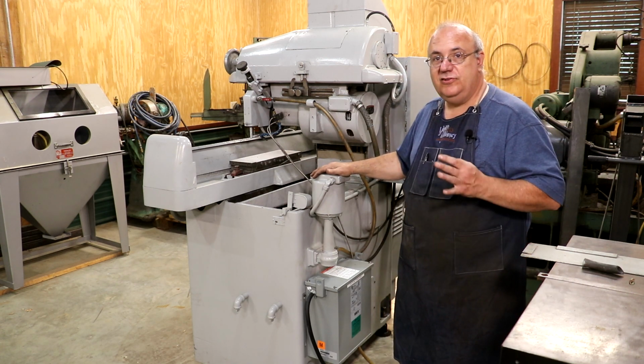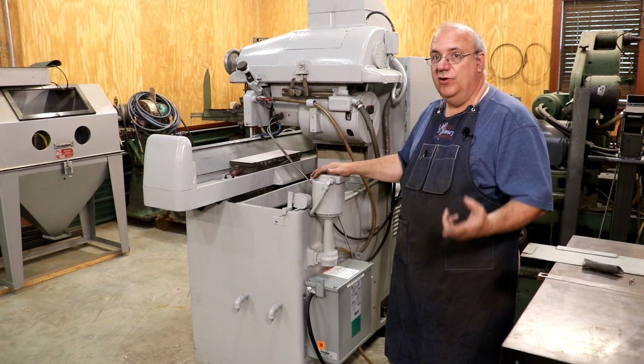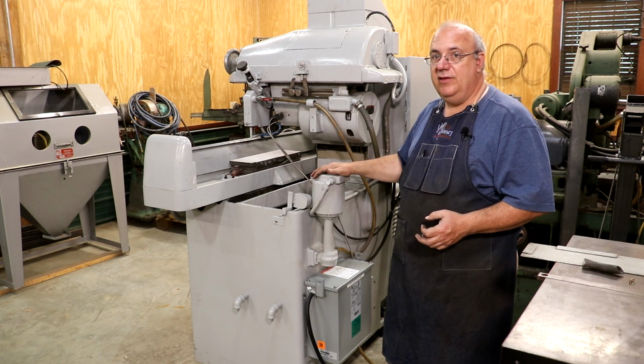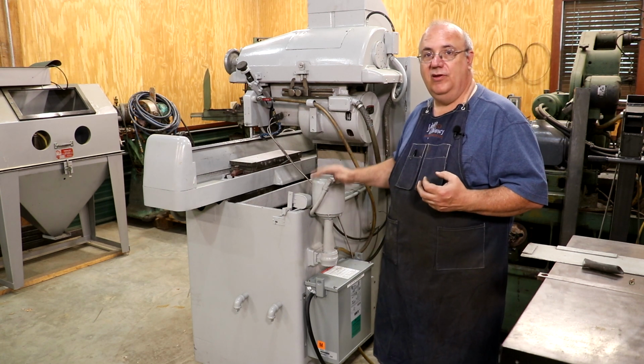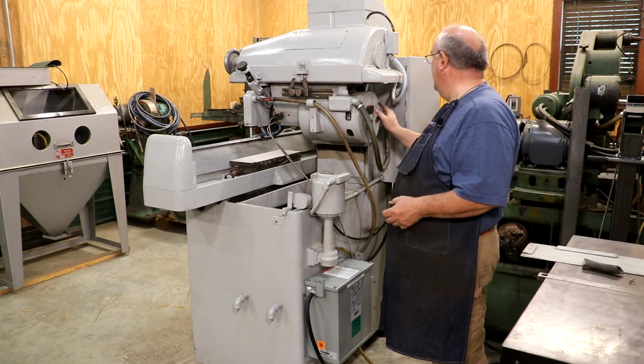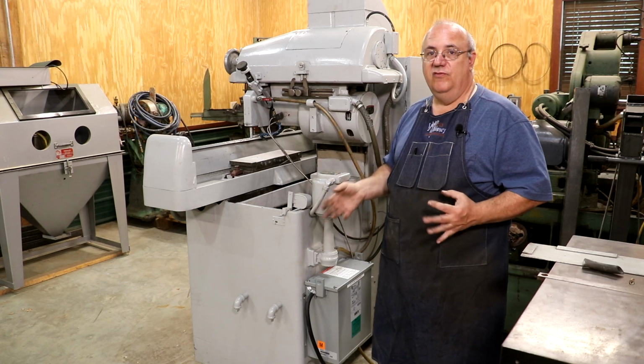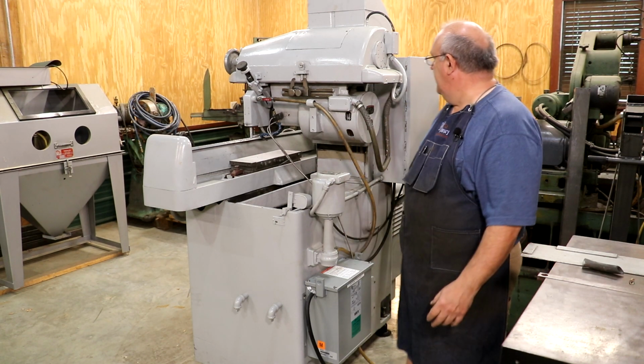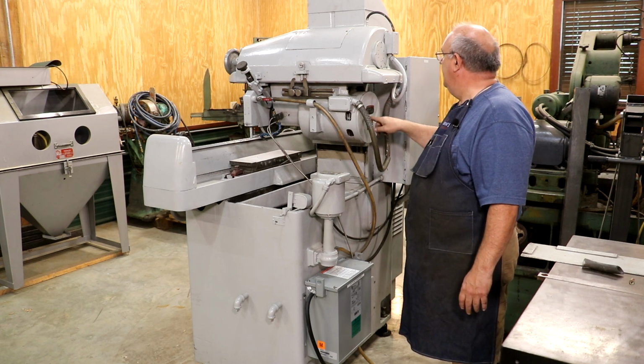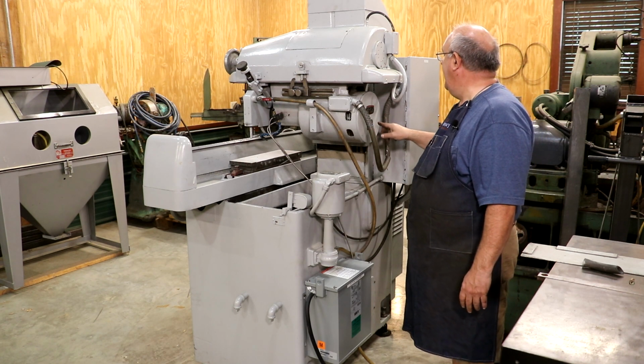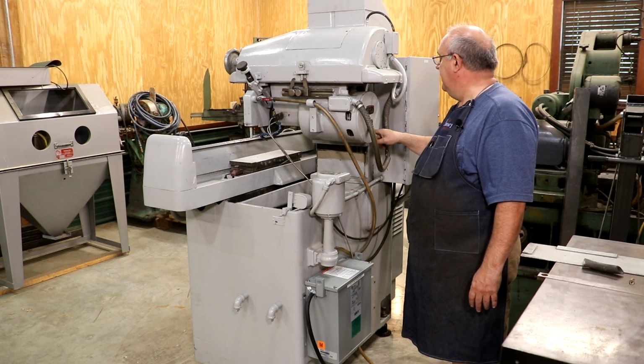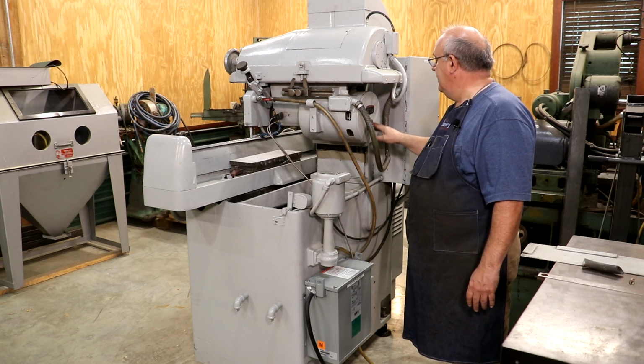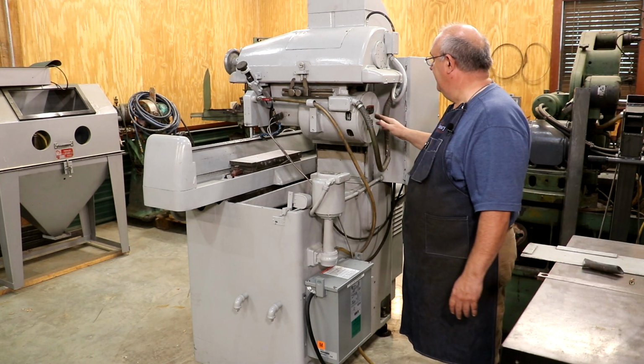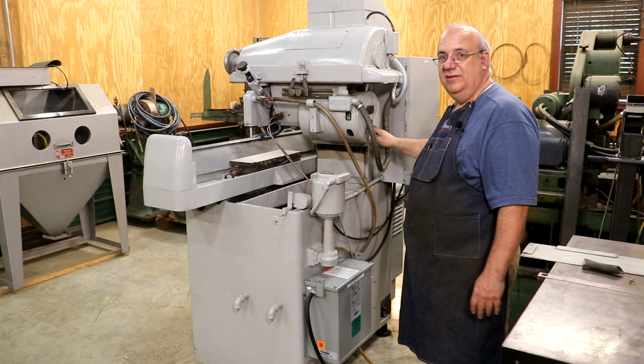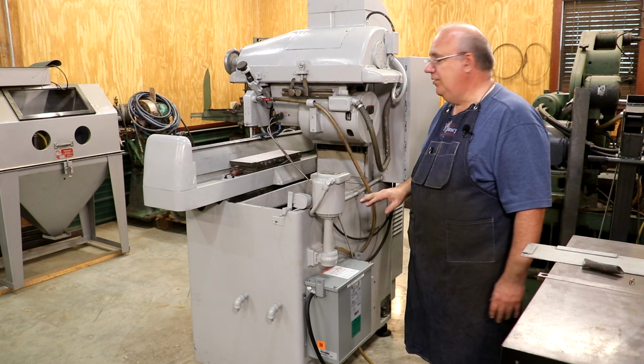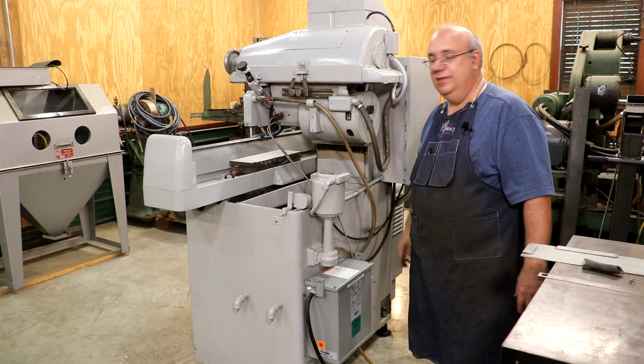Now why is that? Well, most three-phase motors are dual voltage—you can run them on either 220 or 440 volts depending on how the wires are connected in the motor. Coming out of the motor there are 9 wires, and usually a diagram on the motor plate tells you which wires go together for 220 or 440 volts. This spindle motor is 440 volts only, and it's actually a dual speed motor—it will run at two different RPMs, though I don't really know why since we're not utilizing that feature here. But because it's a dual speed motor, it will only run on 440 volts, at least according to the nameplate.